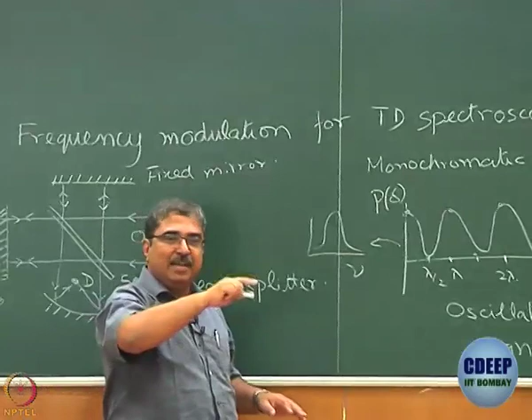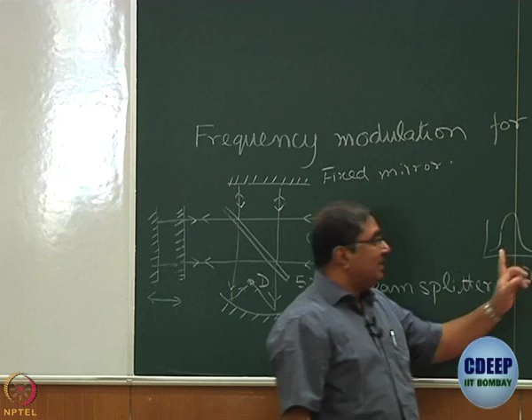Speed of the mirror, what will it determine? Actually, you measure slower, say take the same travel of the mirror. Generally in commercial instruments, you cannot change the travel. In fact, all this comes as a black box, right? So, length is the same. Now, if you cover a 5 centimeter distance in one step, that is one situation, and you cover 5 centimeter in 50 steps, which one should be better? 50 steps should be better, because resolution here would actually depend on resolution here.